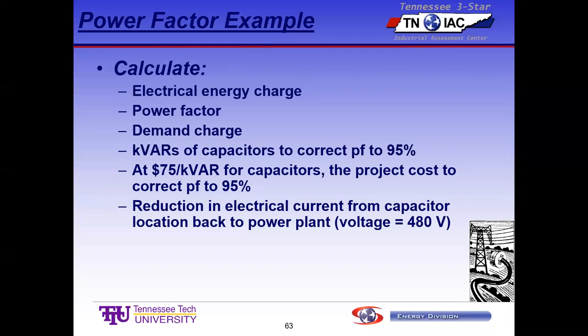And what's the reduction in electrical current from the capacitor location back to the power plant? Because that's where you get the benefit, from the application of the capacitors back to the generating plant.